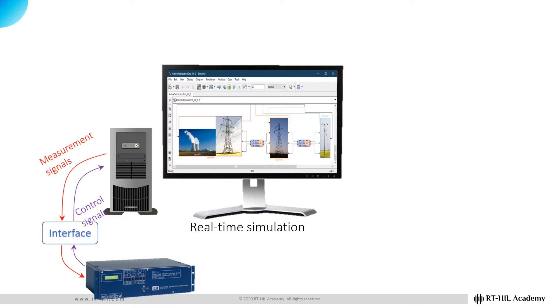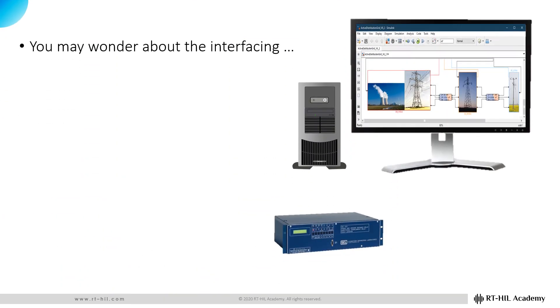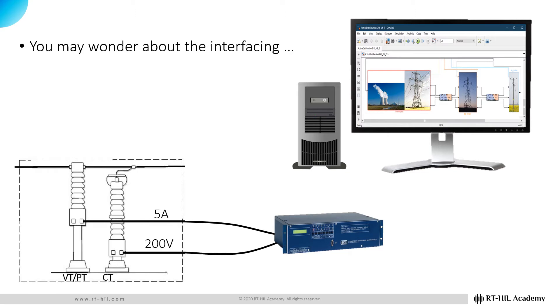Because the real-time simulation is interfaced with a hardware, the whole setup is called a real-time hardware in the loop, or RT-HIL, simulation. You may wonder how the simulation is interfaced with the actual device. Keep in mind that a commercial-grade device is designed to interface with other actual devices in the field. For instance, the device shown in this example expects to receive electric current measurements in the level of a few amperes, and voltage measurements in the level of a few hundred volts, from current and voltage transformers in the field.